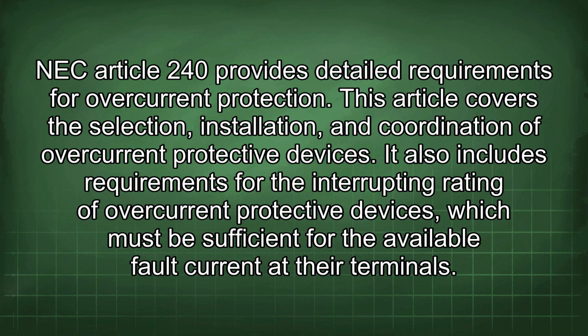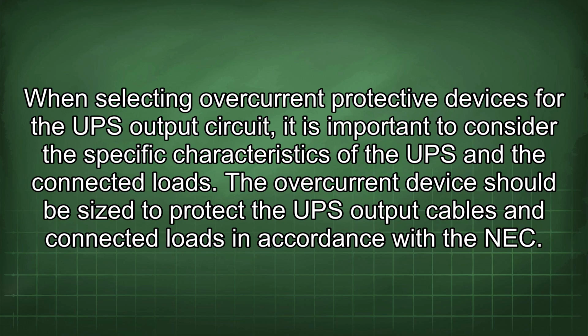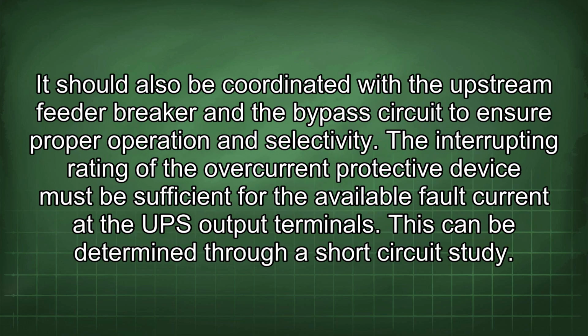This article covers the selection, installation, and coordination of overcurrent protective devices. It also includes requirements for the interrupting rating of overcurrent protective devices, which must be sufficient for the available fault current at their terminals. When selecting overcurrent protective devices for the UPS output circuit, it is important to consider the specific characteristics of the UPS and the connected loads. The overcurrent device should be sized to protect the UPS output cables and connected loads in accordance with the NEC. It should also be coordinated with the upstream feeder breaker and the bypass circuit to ensure proper operation and selectivity.